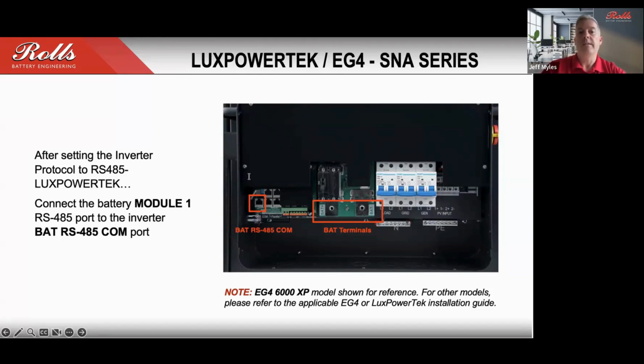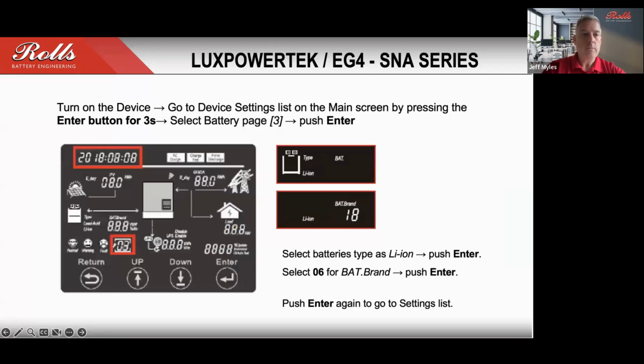And then in the event that you do run into a problem when you are connecting to the inverter, you're likely going to see an error indication about communication on the inverter in some way, whether it's displayed on the screen or some alarm of some sort. And that generally is going to be caused by a condition that's probably connected into the CAN port instead of the RS-485, or potentially you need to readjust the wiring for that COM cable to align with the particular inverter that you're working with. So in the case of the SNA series, these units will provide you an alarm. And so the alarm is actually going to be displayed at the bottom.